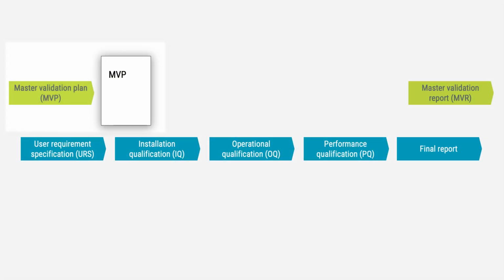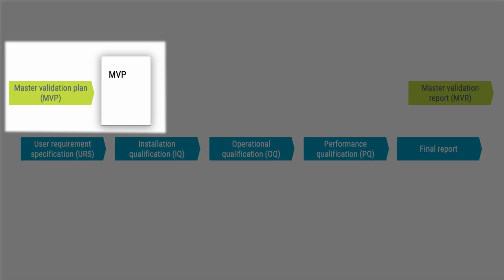Process validation also requires several different types of documents and records, and I'm going to walk you through these now. First of all, there is the Master Validation Plan, the MVP. The MVP defines the manufacturing and process flow of the products or parts that the organization manufactures, identifies the processes that need to be validated, schedules the validation and interrelationships between these processes. The MVP outlines the overall strategy and approach for the validation activities. There may be one MVP for all manufacturing processes and products in your organization, or one per device and process. How you do this is up to your organization to decide.